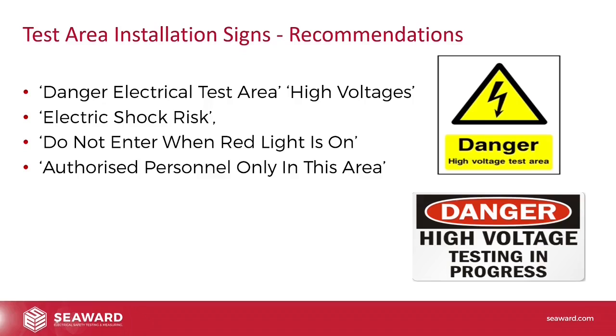Test area installation signs are really, really useful. Things that say danger, electrical test area, high voltages, electrical shock risk, do not enter when red light is on, authorized personnel only in this area. Really good at keeping out non-trained personnel and advising them that the equipment is dangerous. It might not look particularly dangerous, but it is, so we need to make sure that people are aware of the danger.